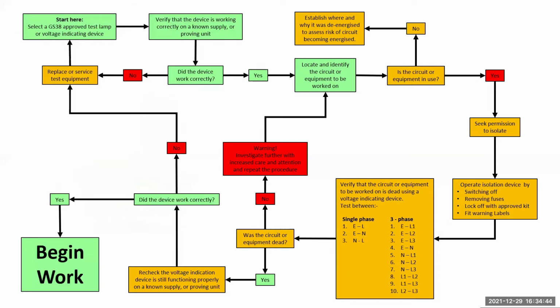If the circuit was dead, you now need to reprove your voltage indicator. Again, consider this. How would you know if the tester was working properly? Because the circuit was dead, so no LEDs would have lit up. Either that, or your voltage indicator developed a fault while you were using it, and this is what you need to do to prove that it worked one last time. If the device is working, you can begin work. If not, you need to carry out a risk assessment, make safe, and then replace or service your test equipment, possibly even starting the process again.